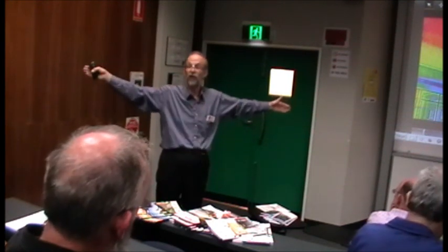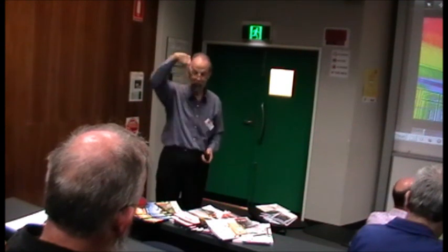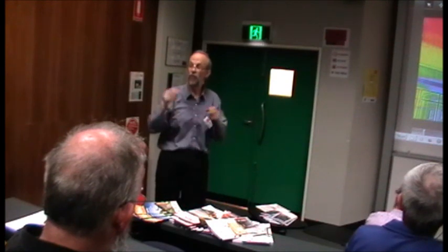But this is again one of the problems of tables. Sometimes you'll find wonderful tables. We saw those two numbers in that camera of mine for aluminium. There are tables which will give you about 6 different conditions of aluminium. But some were done with wavelengths of our camera, some with wavelengths of my old camera, some with a whole range of wavelengths. In fact, they basically say the whole lot. Some are taken looking straight down, some looking at an angle, some taken when the aluminium was at round room temperature, others at about 300 degrees C. So you can't always be sure what the numbers mean. That's where we have a problem. So sorry, I can't answer that question for you with these cameras.